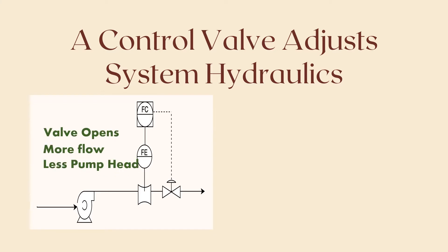If there is no control valve, the pump will face the minimum resistance, which means pumping much more flow than expected, and may even cause the pump to work at the end of the curve, which is not a good operating condition in many cases. I have made a dedicated course for pump hydraulics where it plots the pump performance curve against the system curve, and shows how the control valve on the discharge affects the pump operating point. You can check it out in the description.